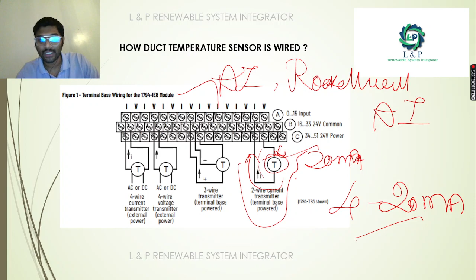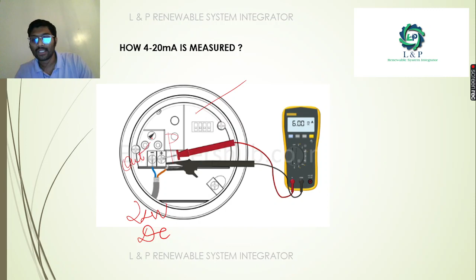As we said earlier, consider this a 24 volt DC supply, and this is your sensor. As you can see here, this is installed in the duct. These are the two provisions you have: one is a power provision, and the other is the output provision. As I said earlier, the 24 volt DC output goes to your temperature sensor. Connect your commons directly, change the probes in the digital multimeter to the current and common connections, and change the setting to milliamp, then connect your positive here and the negative here.